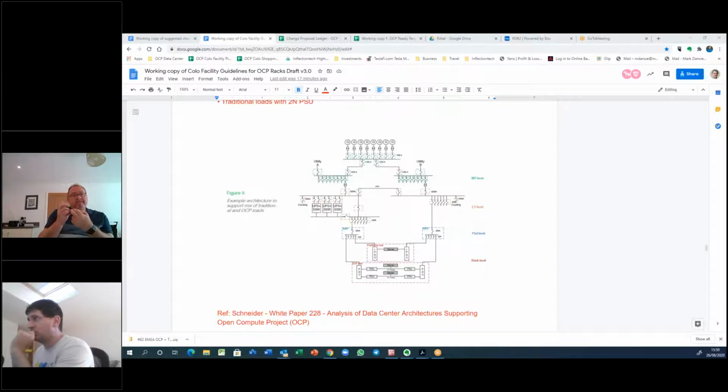Okay. Mark, regarding my point, I looked it up in my notes. Sorry, Stein here. I got the reasoning behind it, and I put it in the remarks in the chat section. It's all about those studies, arc flash, coordination, short circuits. They are getting more and more important, so that when a data center is assessed as OCP ready, those studies should be made. It should be clear what rack and what rating the racks can handle or expect in a short circuit situation, because it's getting more important. The racks will use the power. In the old times it was not so important, maybe because the rack power was not used, but in a proper data center now, and also maybe with the UPS in the rack, it should be totally clear what the interconnection can expect from both sides.